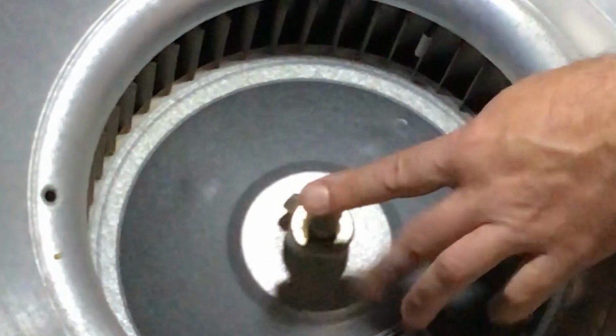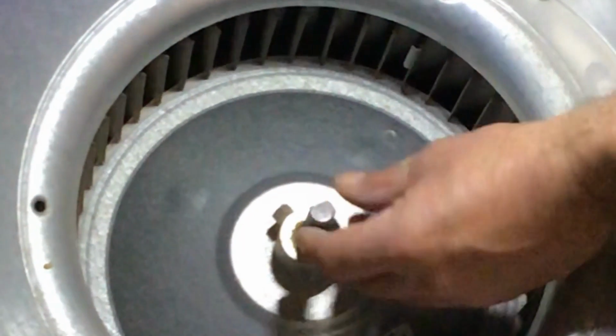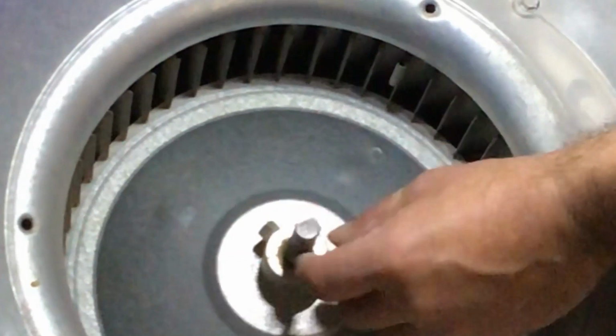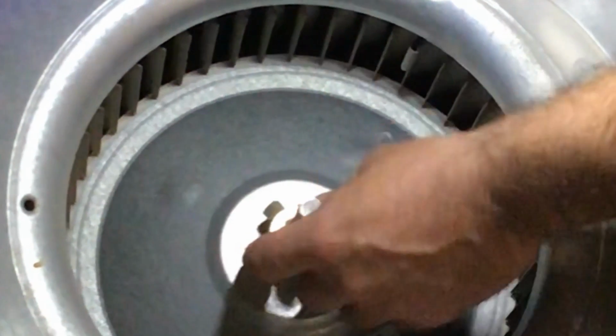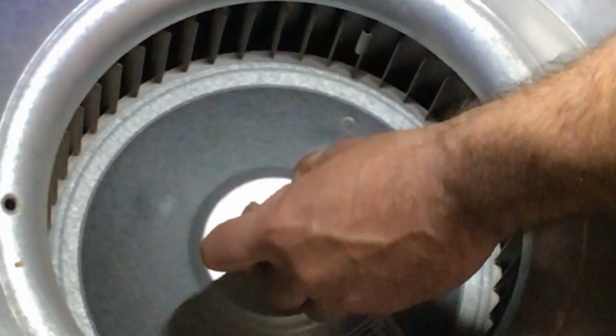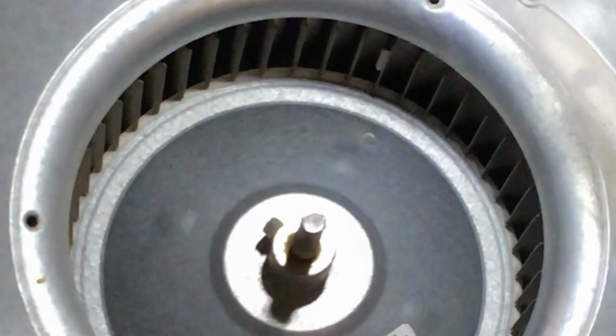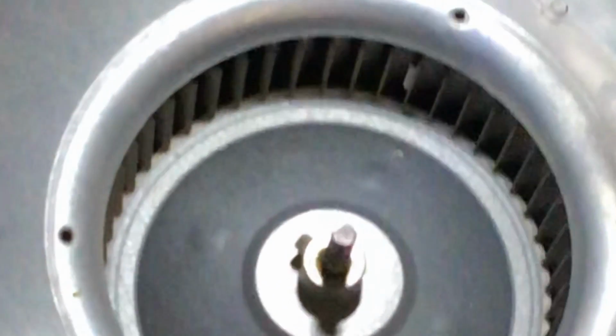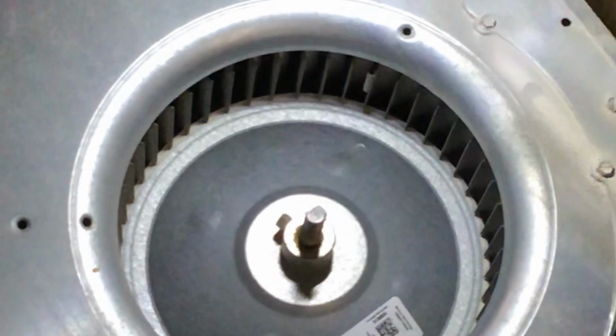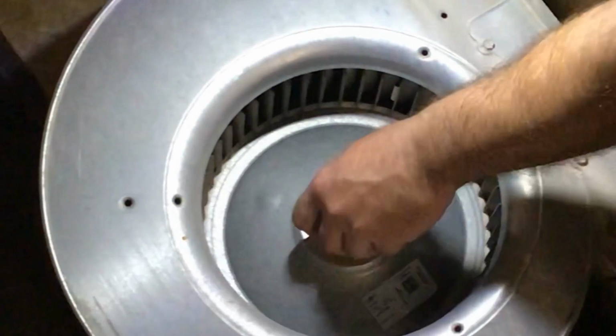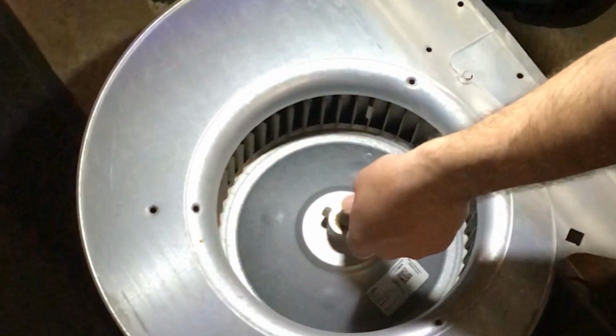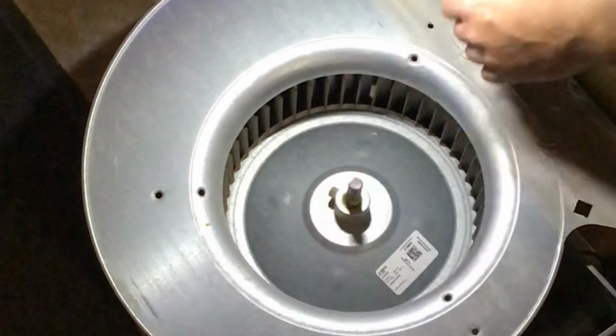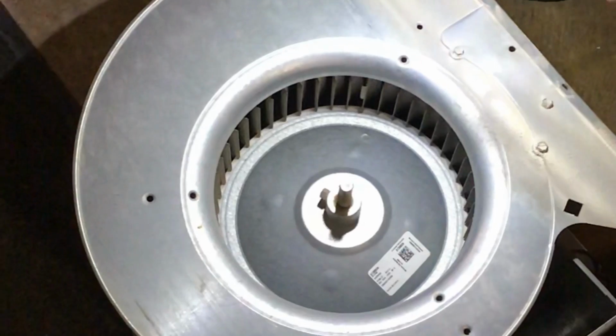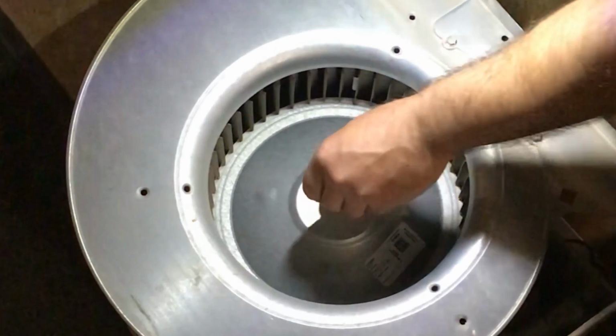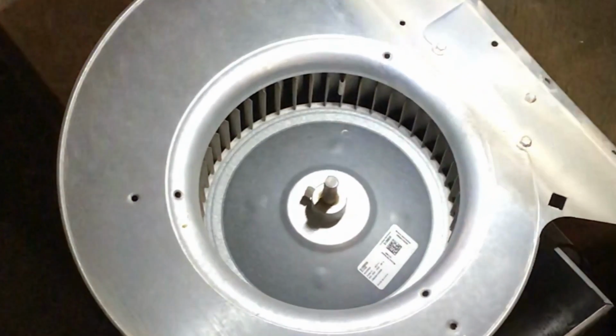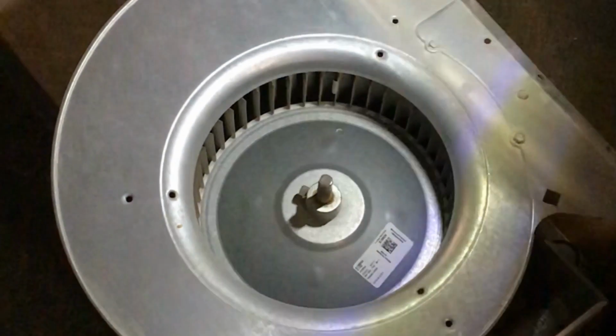Never strike this with a hammer. If you maim this shaft in any sort of way, it will not fit back through this hub, and then you're going to have to replace the whole housing and everything, which is a lot more expensive than a motor and a bit of a pain in the butt. So never strike this with a piece of metal, a block of wood maybe. But you do not want to damage this or even scratch it on the sides, or you're going to have a hard time getting it out.